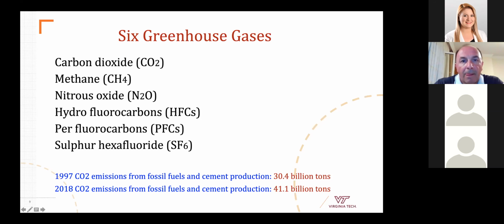There are other global warming gases as well: methane, nitrous oxide, hydrofluorocarbons, perfluorocarbons, and SF6. We are power engineers, many of us. We know we use SF6 for compact power substations and switchgear. At a substation exposed to the outside, to avoid sparking, you spread components out. But if you do a substation indoor or underground, you don't have that much space, so you use SF6 to protect against sparking. That's the use for SF6 in our industry.